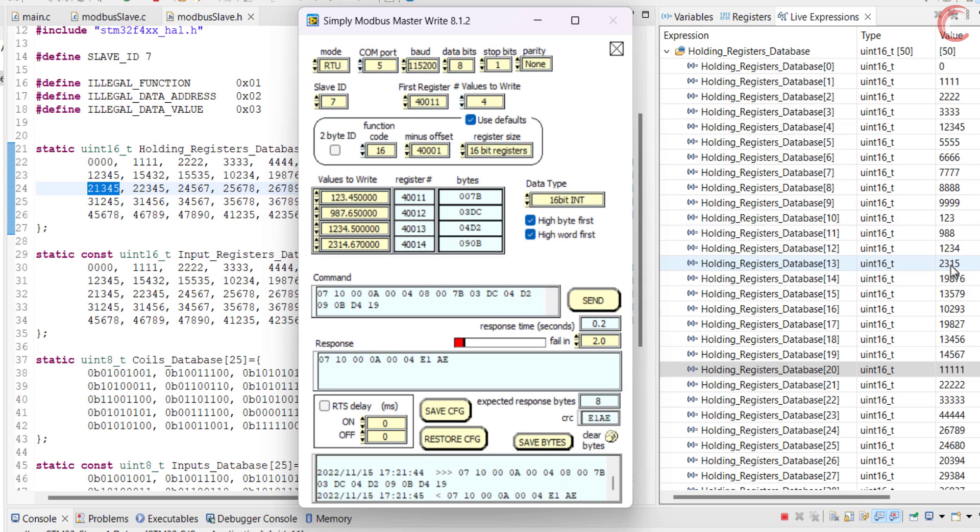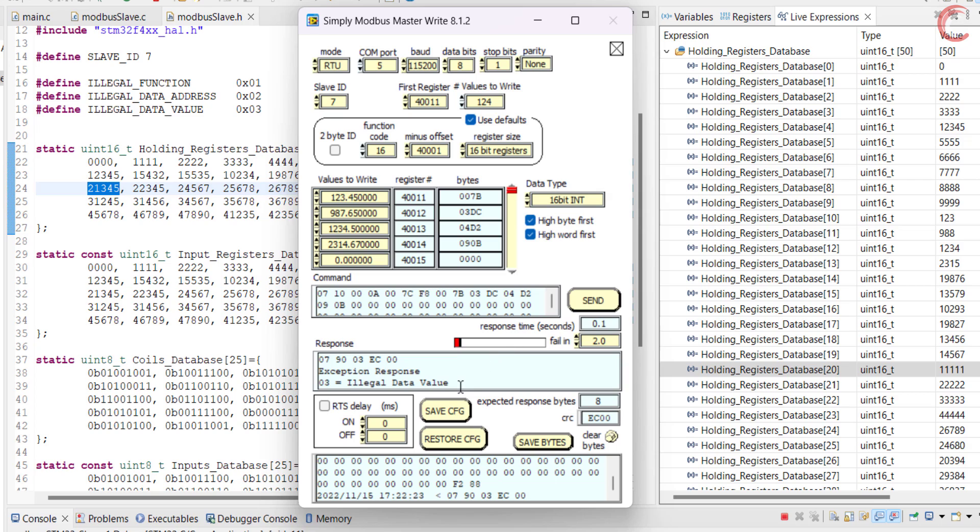Now let's see some exceptions. We know the master can request a maximum of 123 registers, so if it tries to request 124 of them, the slave will send an exception saying illegal data value.